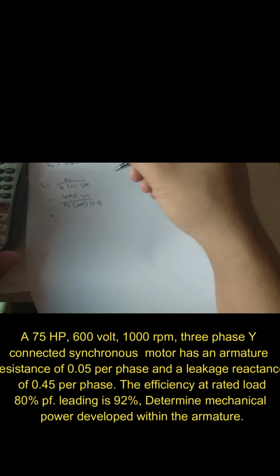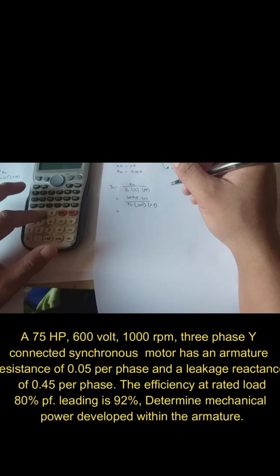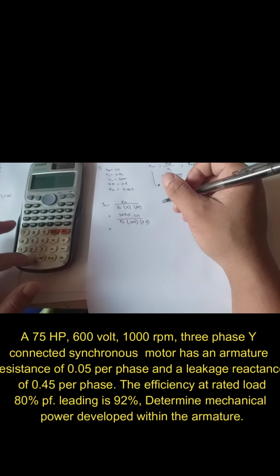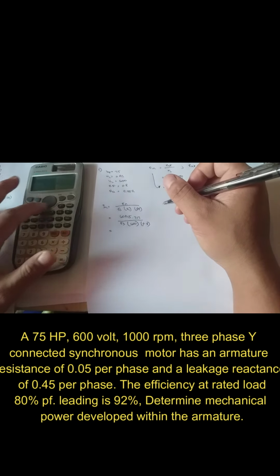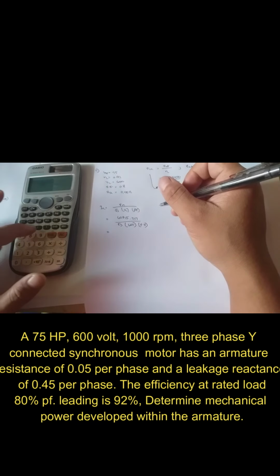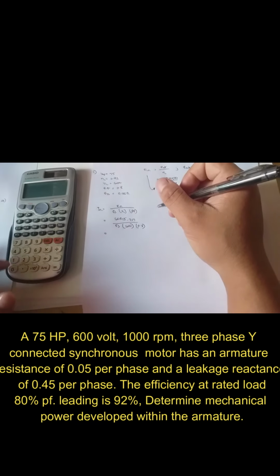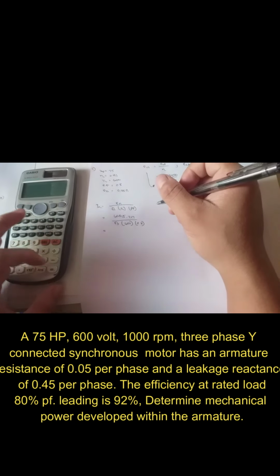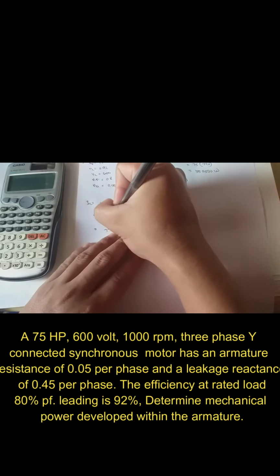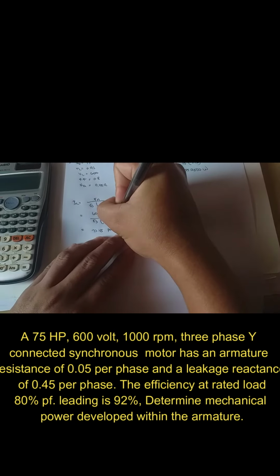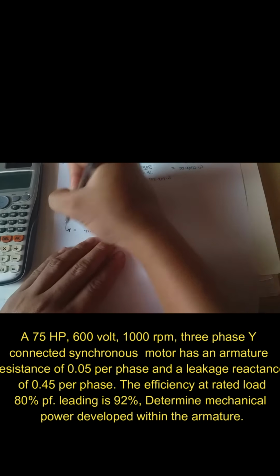So we have 60,815.217 over square root of 3 times 600 times 0.8. We have 73.15 amperes. That's our current rating.